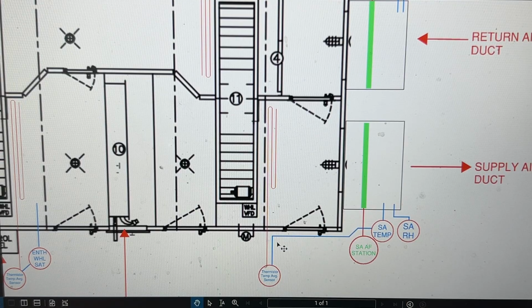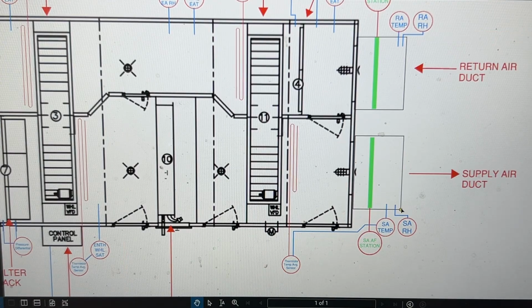So similar to the other one, there's also a thermistor temperature averaging sensor. So again, same as the temperature averaging sensor on the discharge of this wheel, we have the same here, where it's wound uniformly across the wheel to get that averaging temp. And that gets connected to our supply air temperature on our supply air ductwork serving the building. There's also a supply air relative humidity point within there as well. So then it goes and serves all the floors.